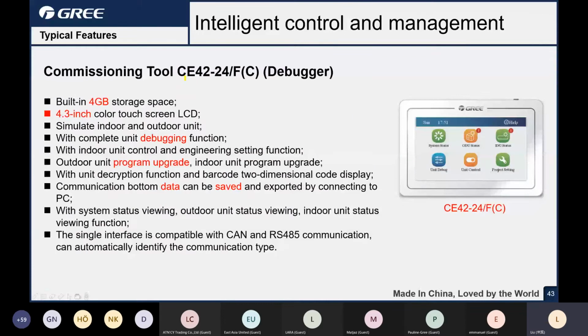Okay. And this is a commissioning tool debugger for the VRF debugging. It has the 4G memory storage inside in the debugging tool, and this is also 4.3-inch colorful display. It can do the debugging. User cable connects with the outdoor units or indoor units. Then you can do the commissioning, parameter checking, and the setting. Everything you can do on the commissioning tool, and even the program upgrade.